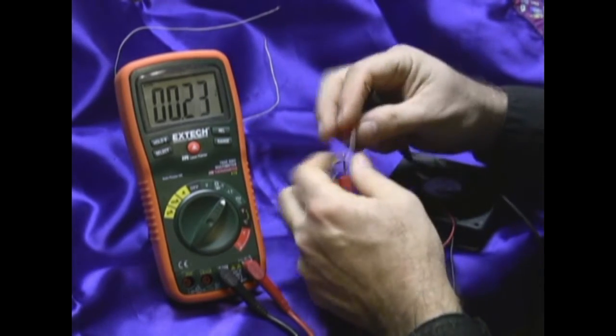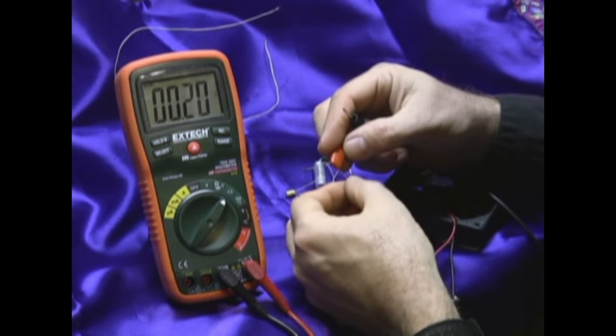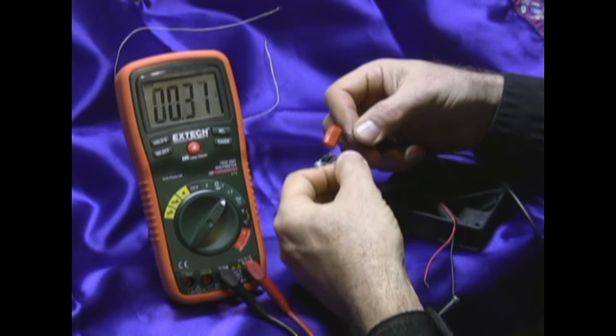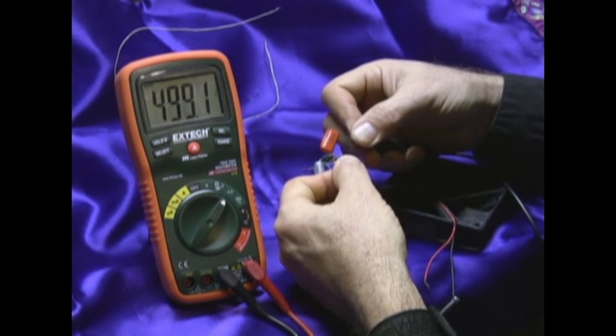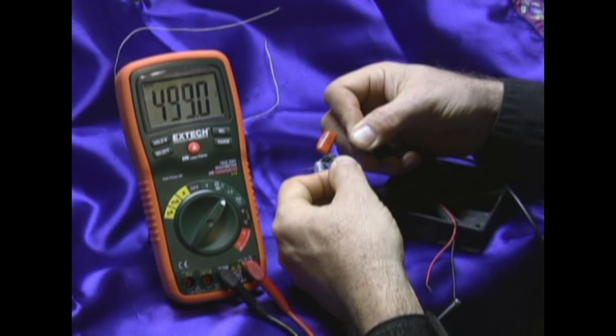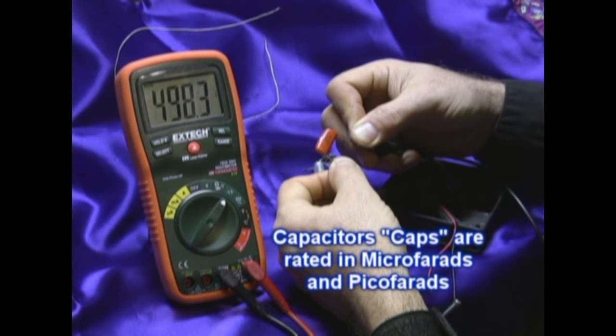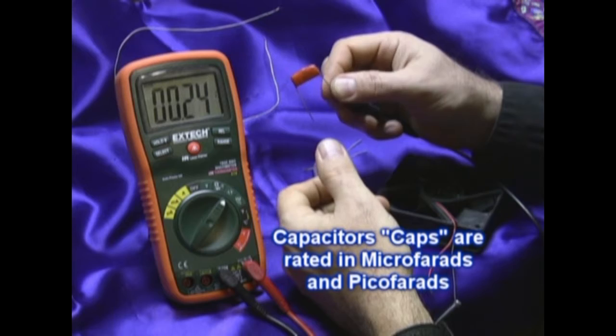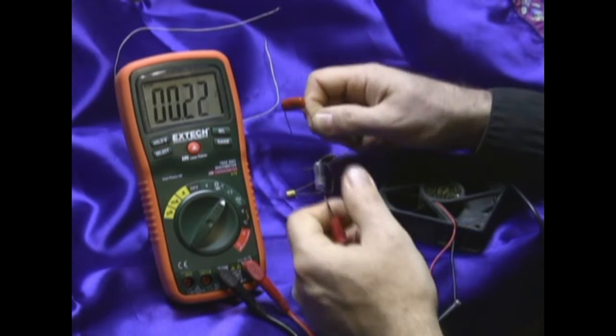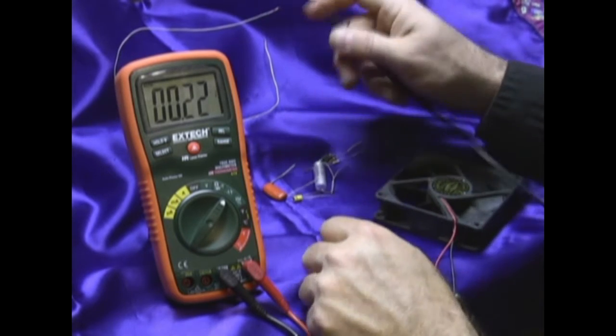Some capacitors don't have pluses and minuses on them because they're not polarized, and you can check those the same way, it doesn't matter which lead is on which. So again, we're reading almost exactly 500 microfarads here, and that's exactly what this is supposed to be. It's not all zeros, and it's giving me a nice mid-range reading, which means the cap is probably good.